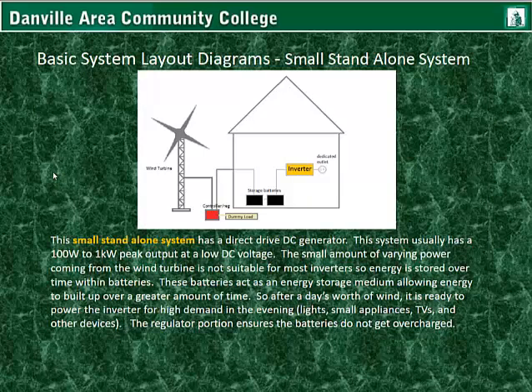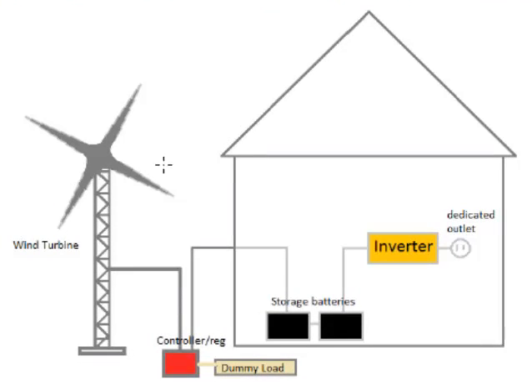Here we get to the basic system diagrams. Here is an example of a small standalone system. This small standalone system has a direct drive DC generator. This system usually has a 100 watt to 1 kilowatt maximum output at a low DC voltage. The small amount of varying power coming from the wind turbine is not suitable for most inverters, so energy is stored over time within batteries. These batteries act as an energy storage medium, allowing energy to build up over time. So after a day's worth of wind, it is ready to power the inverters for high demand in the evening for lights, small appliances, TVs, and other devices. The regulator portion ensures the batteries do not get overcharged. The flow is: DC generator, controller/regulator circuit, storage batteries, inverter, and a dedicated outlet or connection.